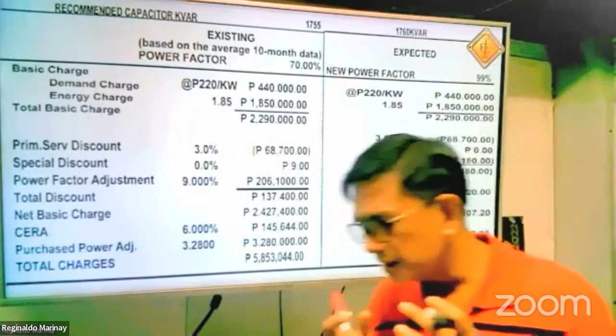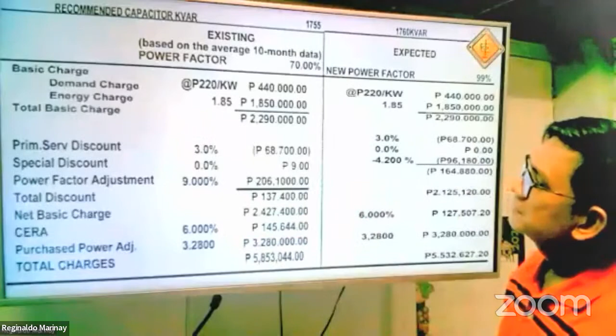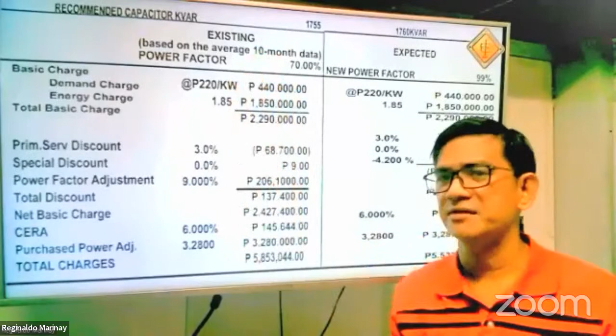Yes, definitely. So there are two columns now: this is the existing, based on the average 10-month data. The power factor is 70%. If that is 70%, it means you will have a penalty or surcharge here because this is lower than 85%.